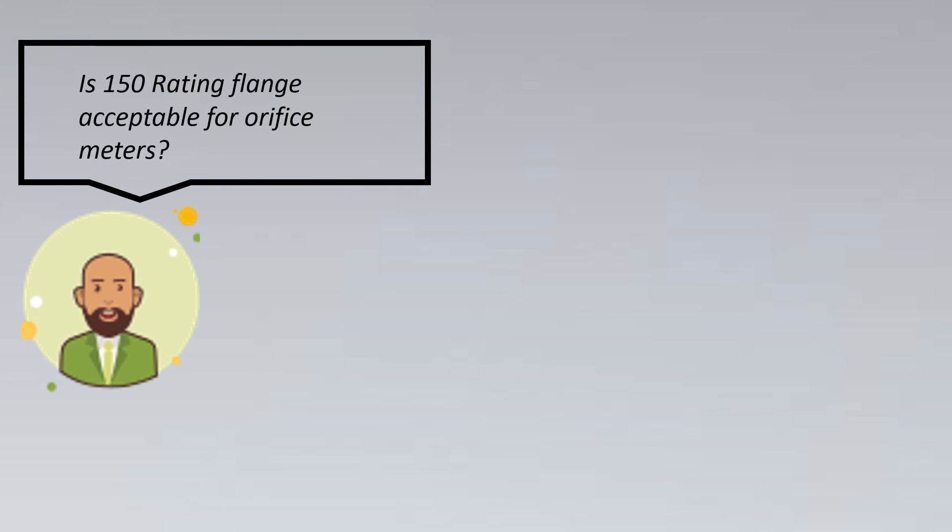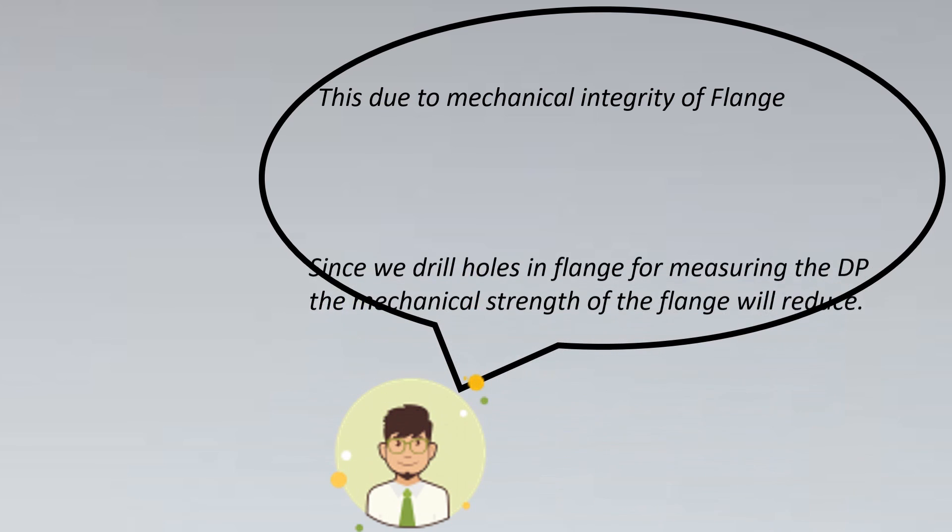Now the next question is: is 150 rating acceptable for orifice meters? You might assume that it could be acceptable, but the answer is no, it's not acceptable. Why? Let's look into why it is not acceptable. The first thing is that for orifice, we discussed that for flange tappings we need to drill the hole inside the flange, so due to mechanical integrity of the flange which gets affected by drilling, we cannot do this thing.